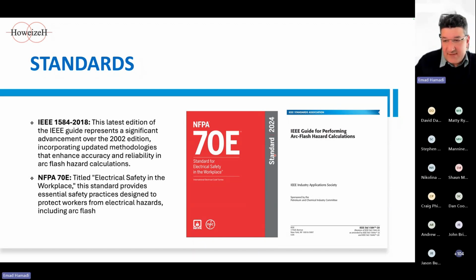There are a few other standards in this field, like DGUV 2003, which I think is the standard used in Germany, or other standards in IEC, like 60947, which deals with the arc flash mitigation system. Or other standards that focus on a specific aspect of the arc flash, like PPE or other aspects. But these standards are typically not used for the calculation of the arc flash study.